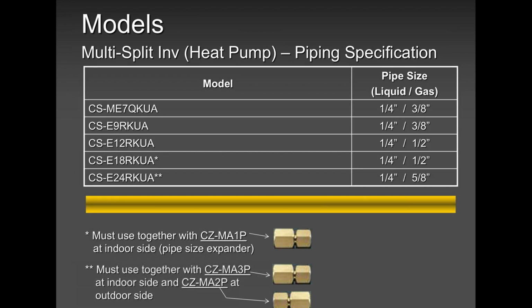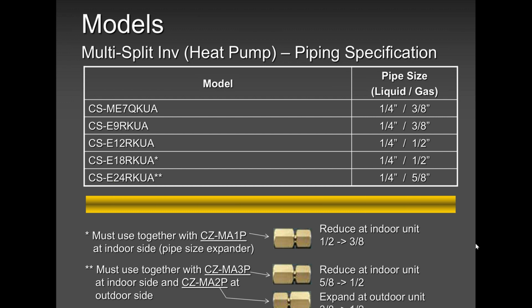Now, here is where you need to pay attention, guys. Why am I saying that? Because our multi-zones are totally different from other competitors. Other competitors are doing it differently, and we are doing it totally differently. If you have installed other guys' multi-zones, you will need to pay attention here, because all we need you to pay attention to is the pipe sizes. If you don't install the correct pipe sizes, you will cut the lifespan of this compressor, the lifespan of this unit. It's designed to work more than 10 years without any failure.